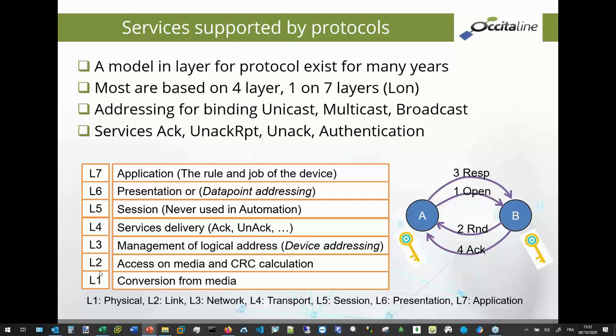And for the KNX and LON, the protocol stack is free, because it's mandatory. You follow different layers. In fact, the certification in KNX and in LON is for layer 7. We will see just after, and BACnet is on the bottom of layer 7. The layer is very important, because all kinds of protocols support or do not support the 7 layers. A model of communication proposes 7 layers. Layer 1 is just a conversion of medium. You can support the twisted pair, the fiber optic, IP, and so on.